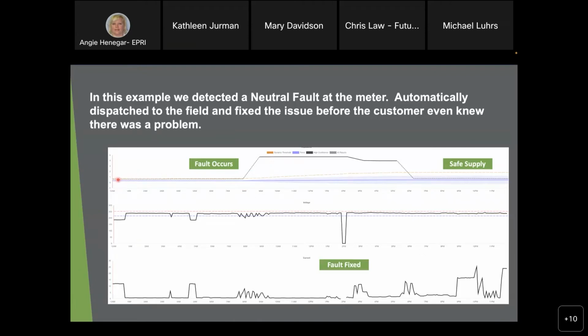So in this example, the impedance is tracking along — you can't really see it, it's like 1 ohm, or just under, which is what that black line is showing. And then something's jumped up, now it's like 4 or 5 ohms. For those not so engineering-centric, that's a lot — if that was a fault on the home and you touched it, you could die. Over here, it has happened, so it's pretty serious. This could be really bad, or your house could be burning down. This kind of jump is quite a serious fault.